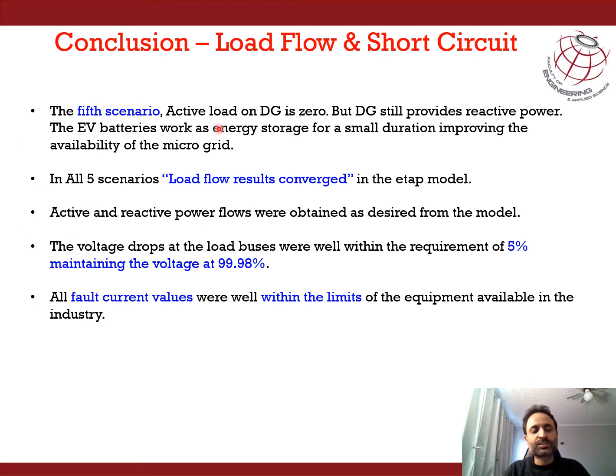The fifth scenario consists of DG sets running in addition to the wind turbines, and the batteries of the electric vehicles supplying the energy demand in addition to the wind turbines. For the case we performed, we showed that the active power of the DG set can be reduced to zero by using power generated from the wind turbines and the EVs. However, we will need the DG supply to provide the reactive power for the induction generators of the wind turbines and the load. One method of substituting the reactive power generation from the DG set is to provide capacitors for supplying the reactive power for short durations.